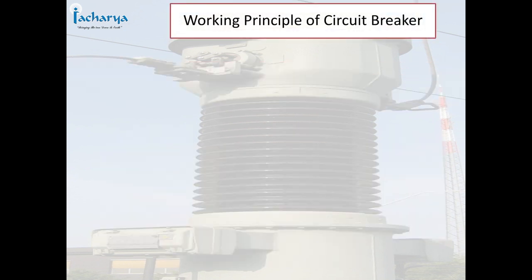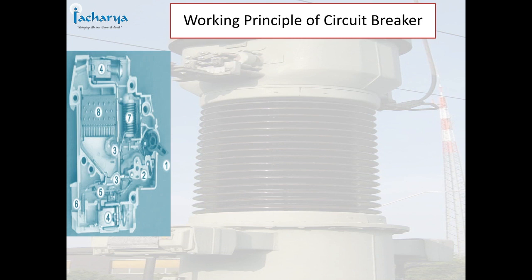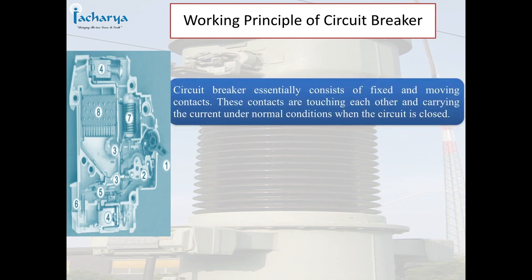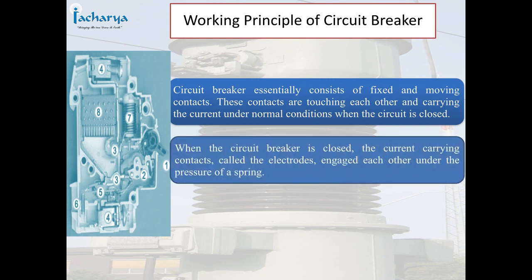A circuit breaker essentially consists of fixed and moving contacts. These contacts touch each other and carry the current under normal conditions when the circuit is closed. When the circuit breaker is closed, the current-carrying contacts, called the electrodes, engage each other under the pressure of a spring.